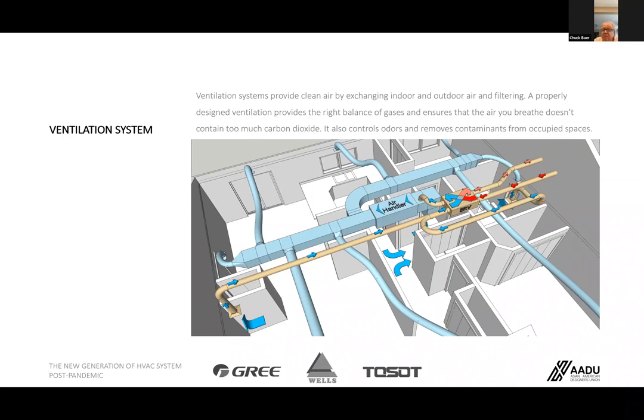But now we have ERVs, energy recovery systems. That allows us to add outside air into the ventilation system, which will help clean up and remove most of the items we're talking about. The average ERV system comes standard with about a MERV 6 or MERV 8 filter, but most of them have the availability to add a HEPA filter. In doing so, we're able to clean up the air in an indoor space up to 99%.